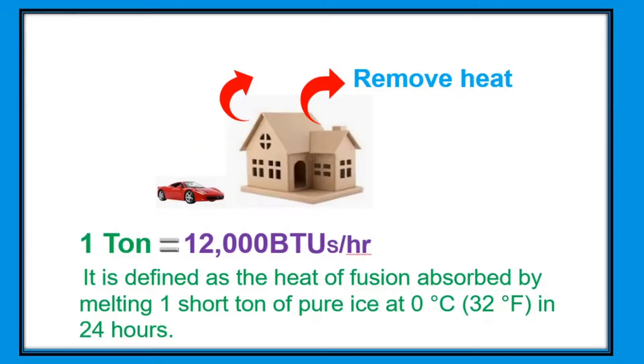1 BTU is the energy needed to heat or cool one pound of water by one degree Fahrenheit at sea level. A ton of refrigeration is a unit of power used to describe the heat extraction capacity of air conditioning and refrigeration equipment. It is defined as the heat of fusion absorbed by melting one short ton of pure ice at 0 degrees Celsius or 32 degrees Fahrenheit in 24 hours.